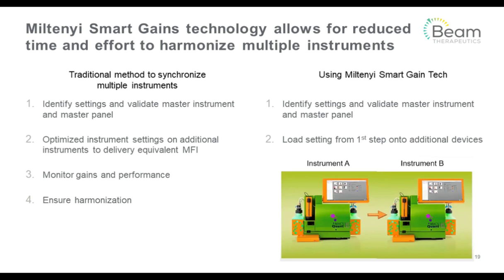You would then have to optimize your instrument settings on additional instruments to deliver that equivalent MFI from instrument to instrument. You would then monitor your gains and performance over time and really ensure harmonization from instrument to instrument and site to site. Miltenyi's SmartGain technology actually allows you to skip some of those, or have confidence in some of your final stages and really do this efficiently.